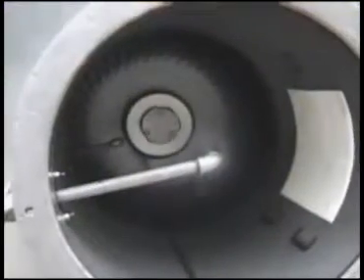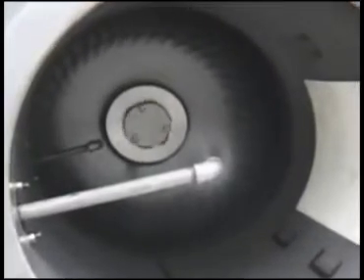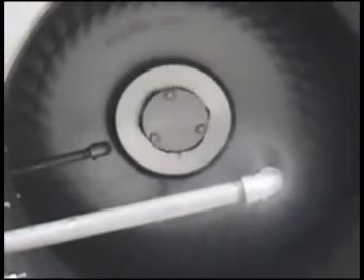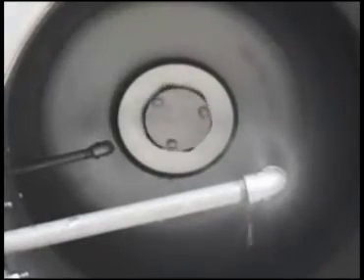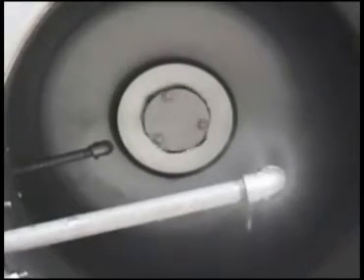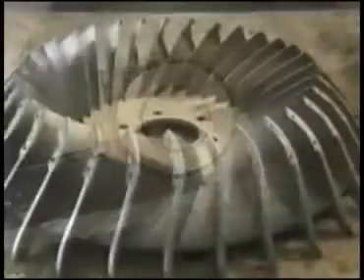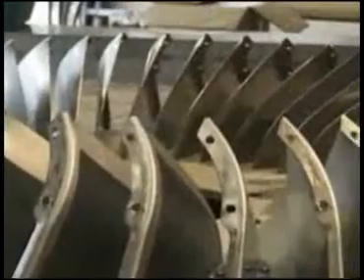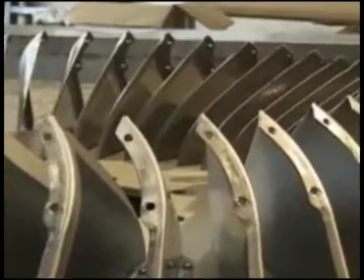The distinguishing feature of the W Rotoclone is the addition of water sprays to the basic principle of dynamic precipitation. The cone spray nozzle at the inlet of the W Rotoclone not only creates a capture mechanism for dust particles passing through the spray, but by continuously supplying a flowing film of water over the specially constructed impeller blades, provides a tremendous surface area for impingement and capture of dust particles. Unlike simple fans with sprays, the W employs a much greater quantity of blades to maximize particulate interception, while the special curvature of the blades ensures that the film of water is distributed for maximum effectiveness.